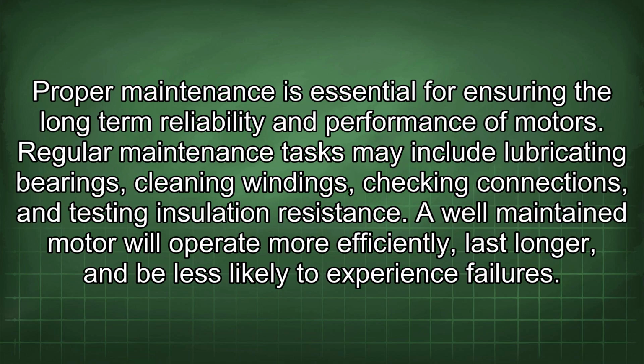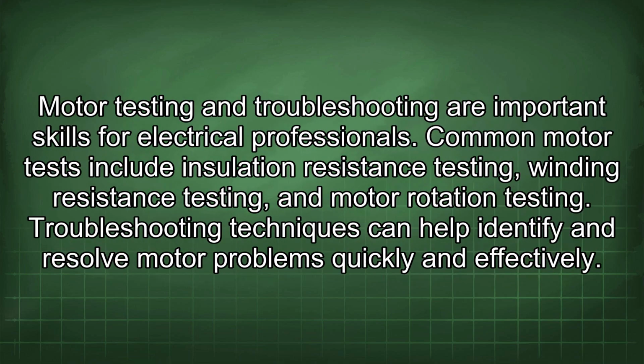Proper maintenance is essential for ensuring the long-term reliability and performance of motors. Regular maintenance tasks may include lubricating bearings, cleaning windings, checking connections, and testing insulation resistance. A well-maintained motor will operate more efficiently, last longer, and be less likely to experience failures. Motor testing and troubleshooting are important skills for electrical professionals. Common motor tests include insulation resistance testing, winding resistance testing, and motor rotation testing. Troubleshooting techniques can help identify and resolve motor problems quickly and effectively.